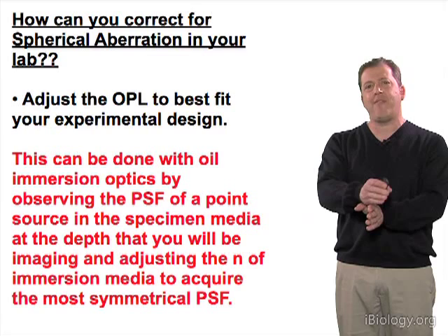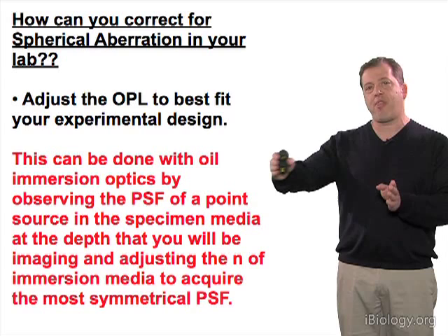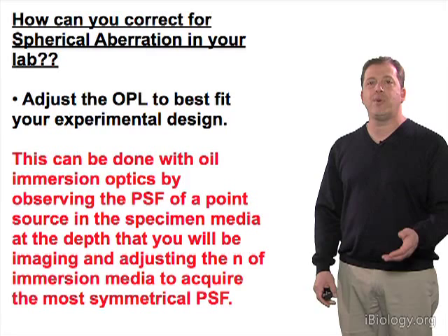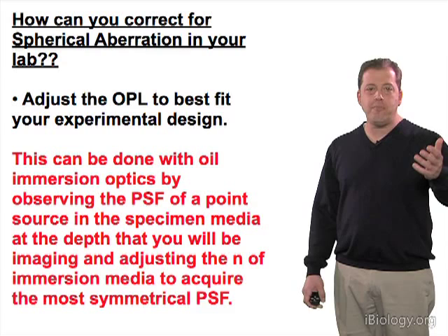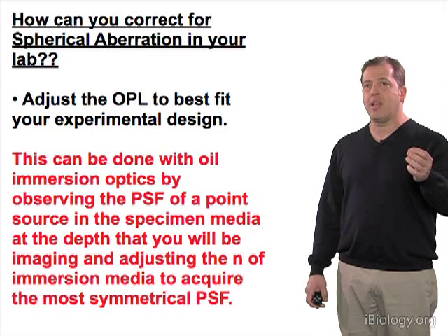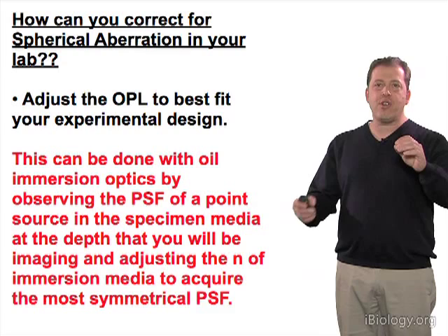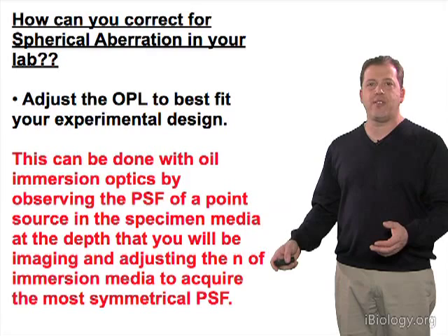We can do that with immersion media. There are kits you can buy which have many different refractive index immersion media that vary at the third decimal place — say 1.515, 1.516, 1.517, and so on. You can look in the specimen at the depth you need, say you're looking at the endoplasmic reticulum, focus to something at the limit of resolution near that depth in the cell, and then test different immersion media at that focus depth to get the best correction for spherical aberration.